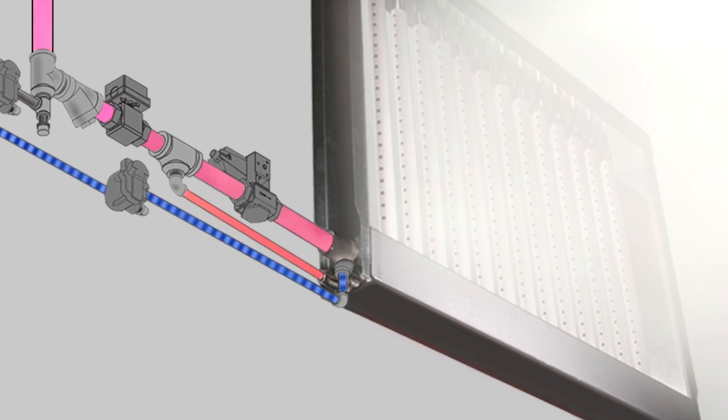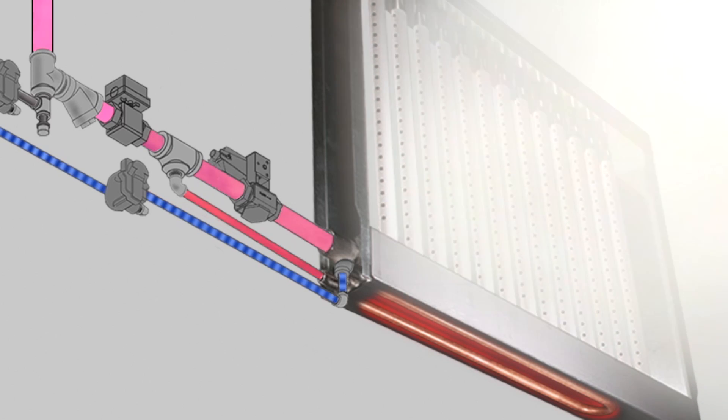There are only two ways for water to leave the Ultrasorb XV. In the form of unpressurized humidification steam entering the airstream, or in the form of pressurized condensate in the heat exchanger returning to the boiler. There is no water to the drain.